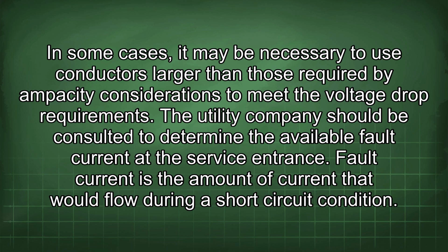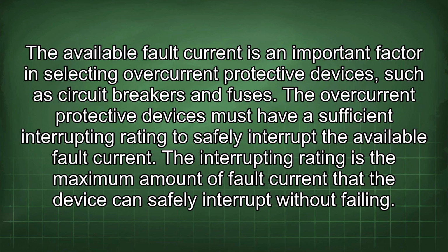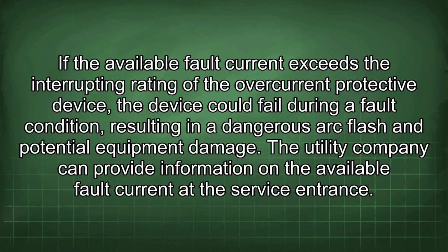Fault current is the amount of current that would flow during a short circuit condition. The available fault current is an important factor in selecting overcurrent protective devices, such as circuit breakers and fuses. The overcurrent protective devices must have a sufficient interrupting rating to safely interrupt the available fault current. The interrupting rating is the maximum amount of fault current that the device can safely interrupt without failing. If the available fault current exceeds the interrupting rating of the overcurrent protective device, the device could fail during a fault condition, resulting in a dangerous arc flash and potential equipment damage.